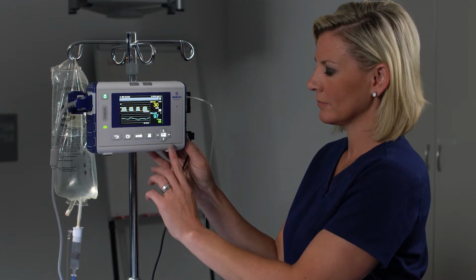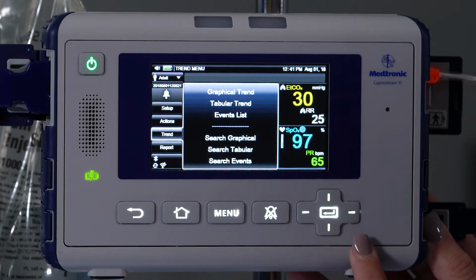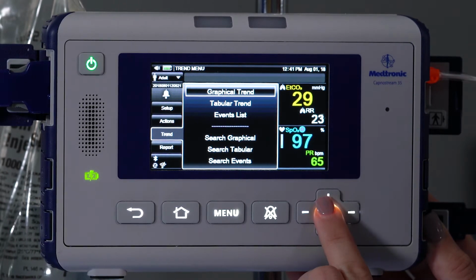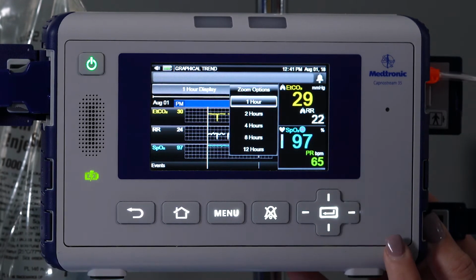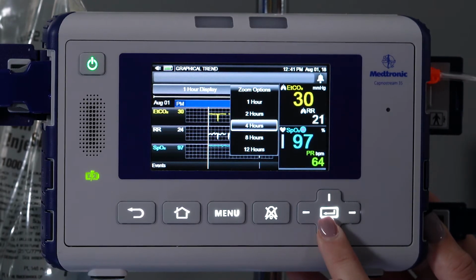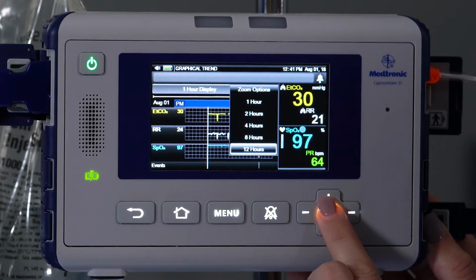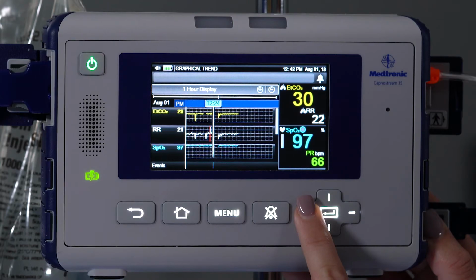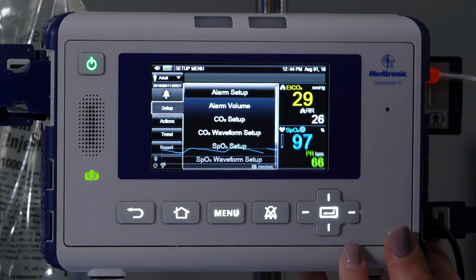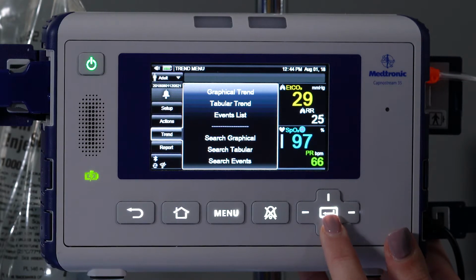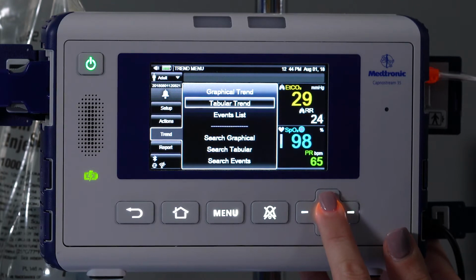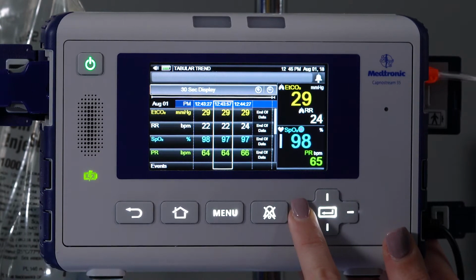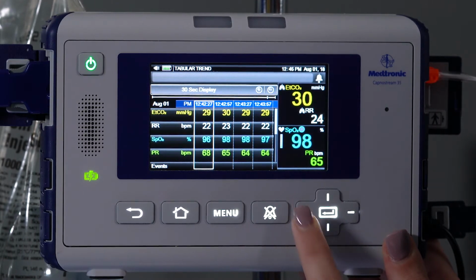To see how your patient is doing over time, there are 2 trend options, a graphic trend or a tabular trend. Press the menu button and select trend on the setup menu. Select graphical trend. You can zoom from a 1, 2, 4, 8, or 12-hour display. To scroll through the trend, use the arrows. For a tabular trend, press the menu button and select Trend on the Setup menu. Select Tabular Trend. Press Home to return to the main screen.